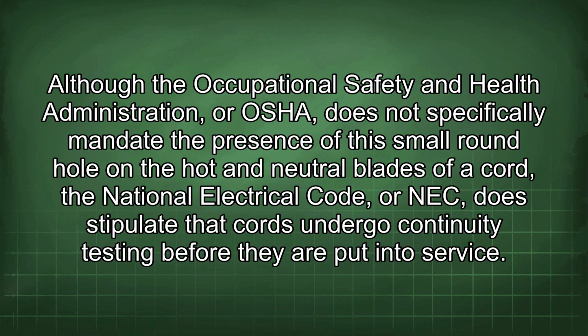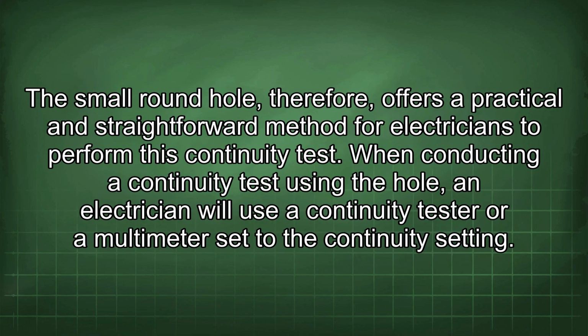Although the Occupational Safety and Health Administration, or OSHA, does not specifically mandate the presence of this small round hole on the hot and neutral blades of a cord, the National Electrical Code, or NEC, does stipulate that cords undergo continuity testing before they are put into service. The small round hole, therefore, offers a practical and straightforward method for electricians to perform this continuity test.